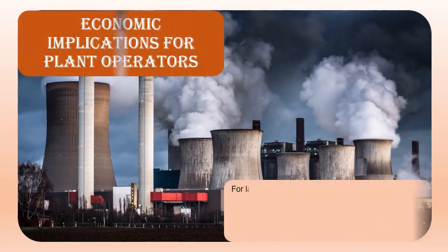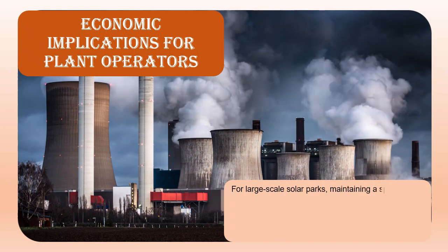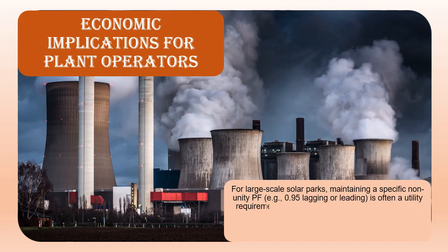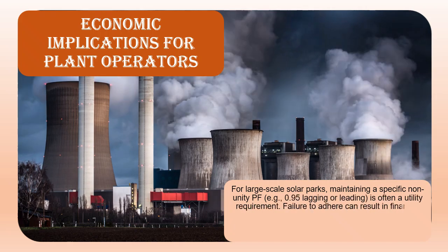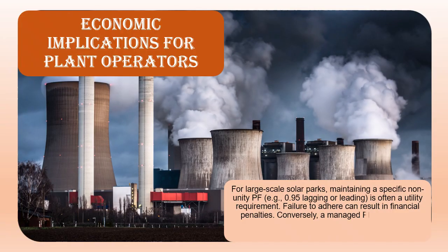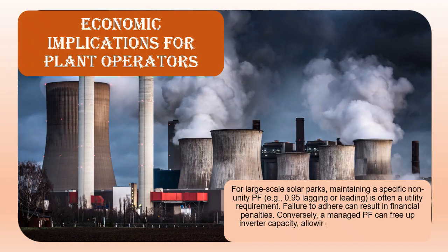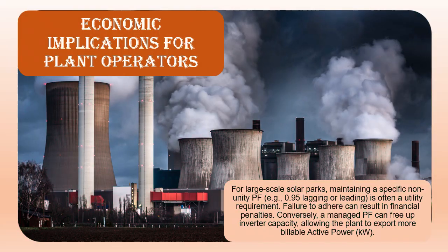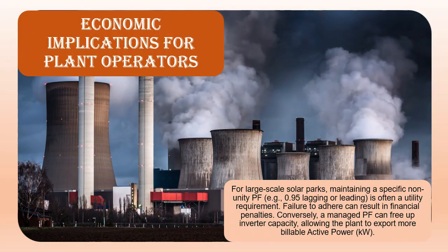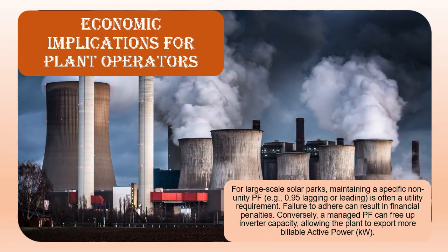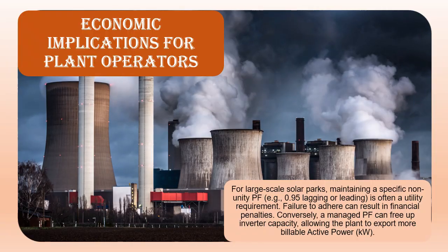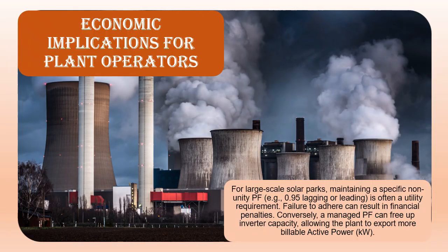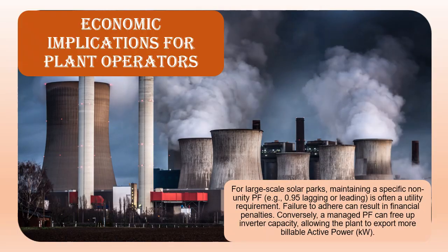Economic implications for plant operators. For large-scale solar parks, maintaining a specific non-unity PF, e.g., 0.95 lagging or leading, is often a utility requirement. Failure to adhere can result in financial penalties. Conversely, a managed PF can free up inverter capacity, allowing the plant to export more billable active power, kW.